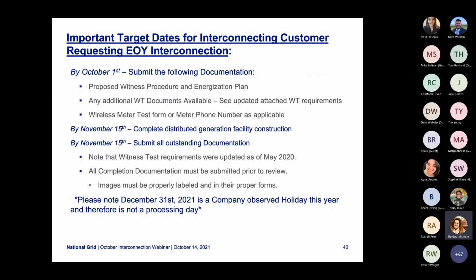These dates have been established based on experience with end-of-year delays, such as engineering reviews, as well as subsequent reviews and revisions as necessary to achieve the interconnecting customer's compliance with the requirements, queuing and resource allocation for both witness test scheduling and meter installations, fewer processing days due to holidays and inclement weather, required registration with ISO-NE for projects over 1 megawatt that must be processed prior to ATI, and interconnecting customer delays in starting the registration process in a timely manner.